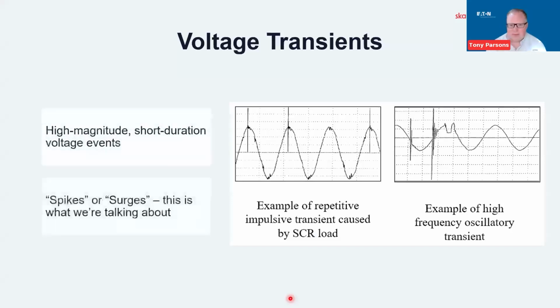We'll come back to harmonics in just a minute, but before we get there, another voltage disturbance to close out this category: voltage transients. Steve showed you earlier that ITIC curve and talked about the envelope where we have good performance in the middle. If you go below the envelope, you're in voltage sag territory. If you go above the envelope, you may be in this voltage transient realm. The difference between a voltage transient and a voltage swell would be the duration, right? These transients are high magnitude, but also very short duration voltage events.